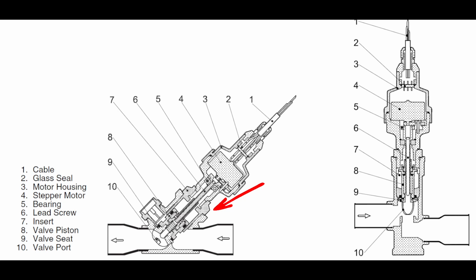You could have something where the valve is occasionally tripping on a refrigerant loss alarm, a superheat issue, something along those lines. If you have a chiller that doesn't monitor suction superheat, it's probably monitoring discharge superheat. It will typically do one or the other, or sometimes both. And you may be having discharge superheat alarms as well. So it may not be just suction superheat. You may have a high or low discharge superheat. And if you're tripping on that, all of those could also be caused by an EXV issue. Or if you're having a liquid level sensor fault where you're not able to make liquid level set point in your evaporator if it's using that.